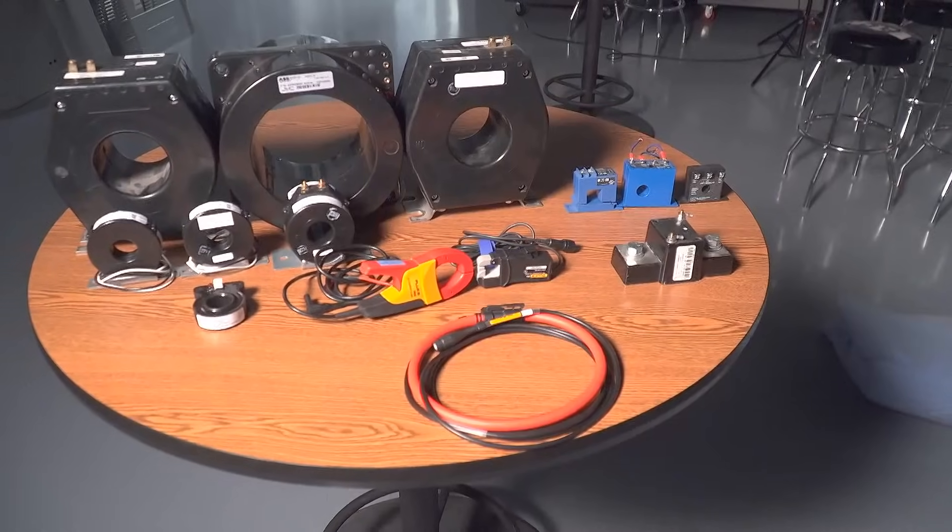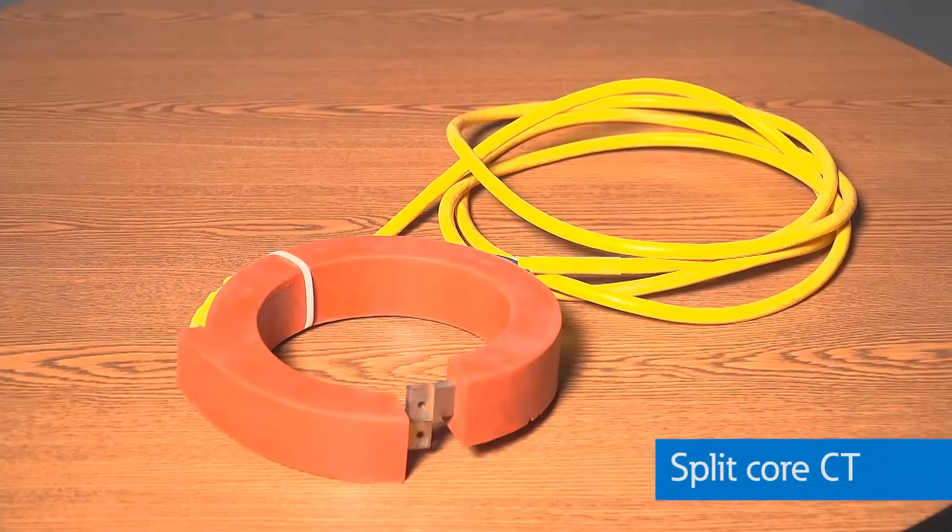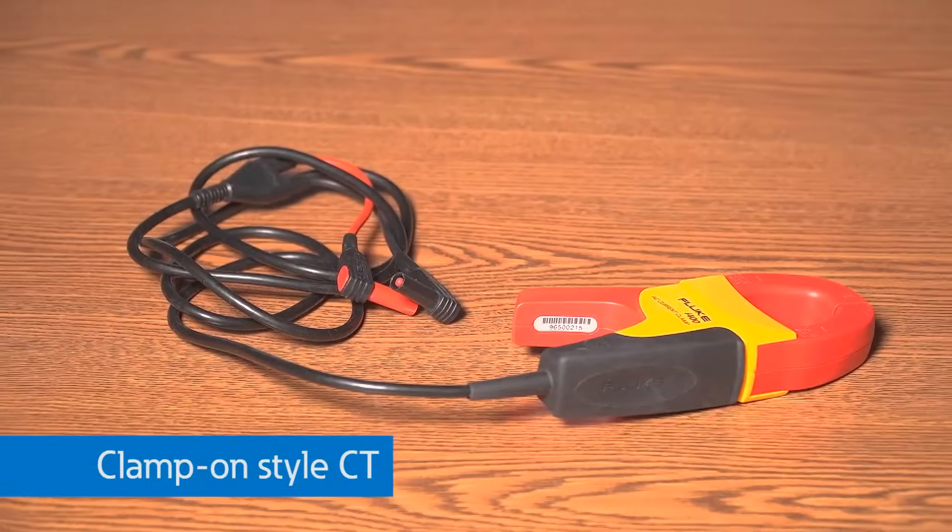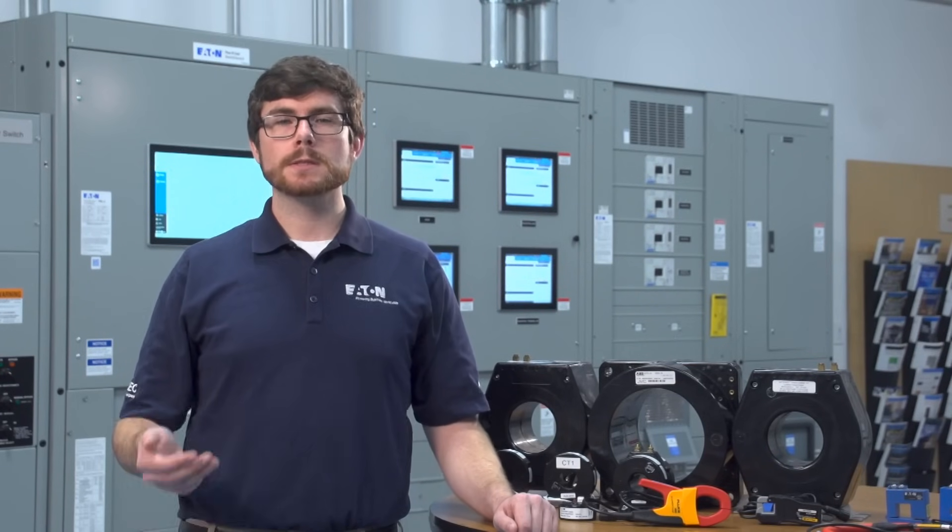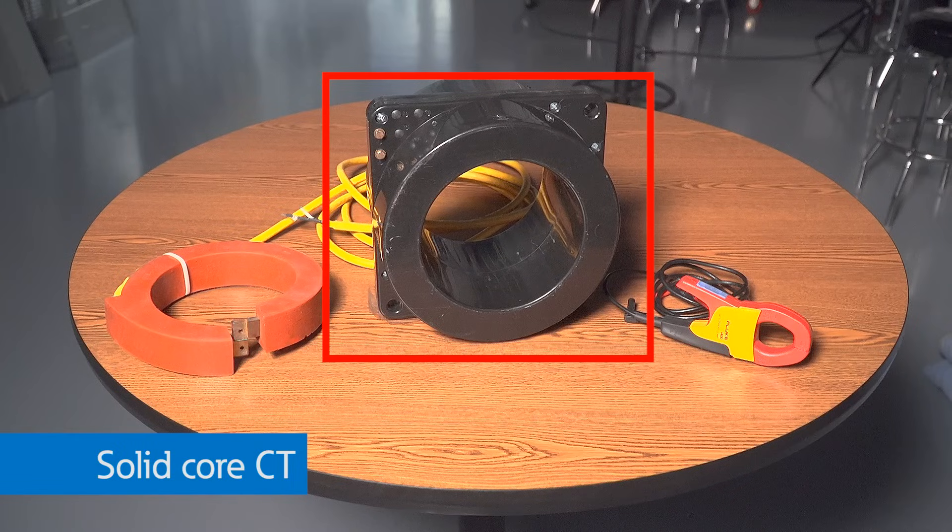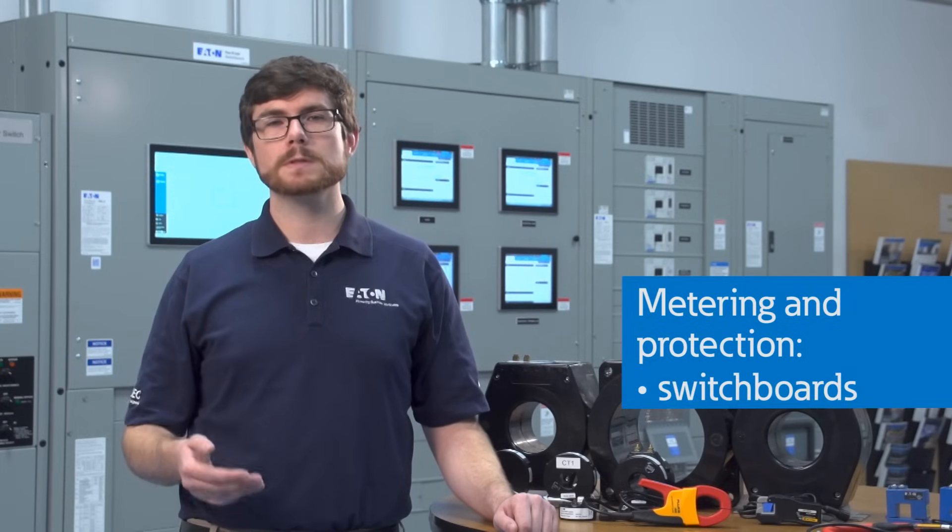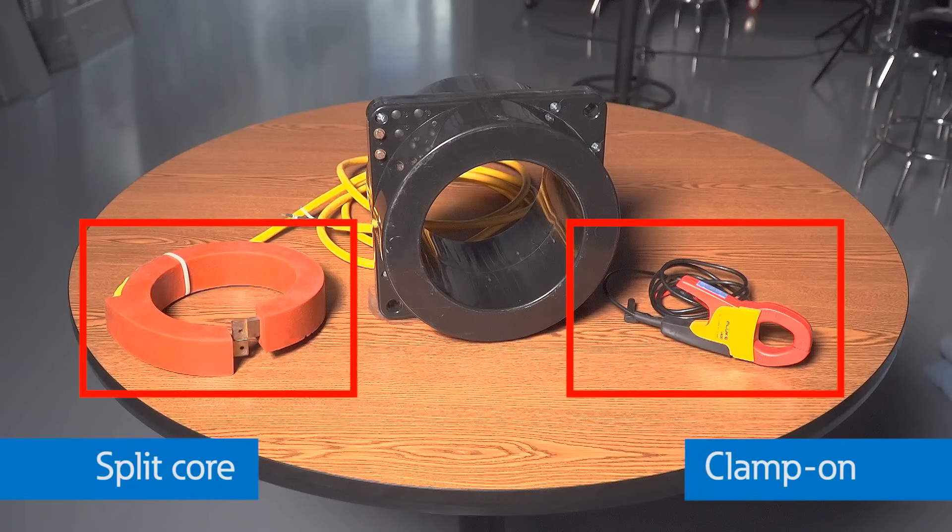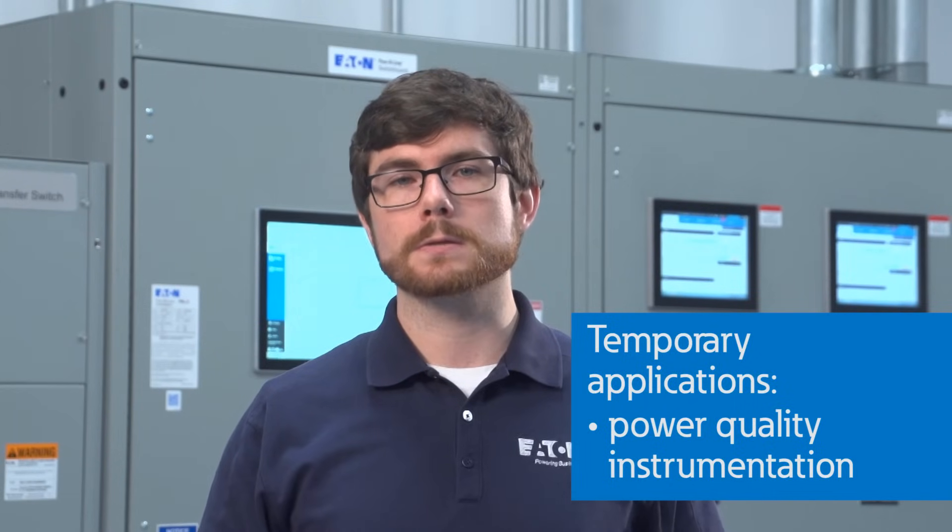Current transformers are primarily used for metering and protection applications and come in various sizes, shapes, and ratings. CTs can be solid core, split core, or clamp-on styles for both low-voltage and medium-voltage applications. Solid core CTs are generally more permanent and are most commonly found for metering and protection in switchboards, panel boards, and switchgear. Split core and clamp-on CTs are generally used in more temporary applications such as power quality instrumentation.